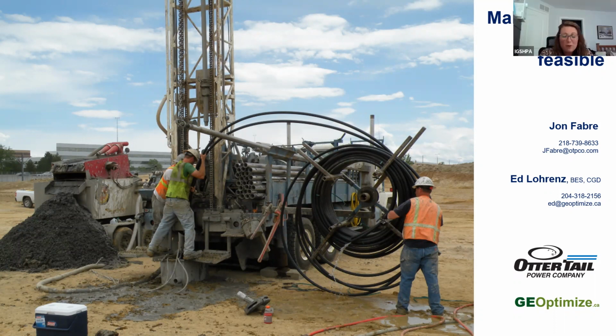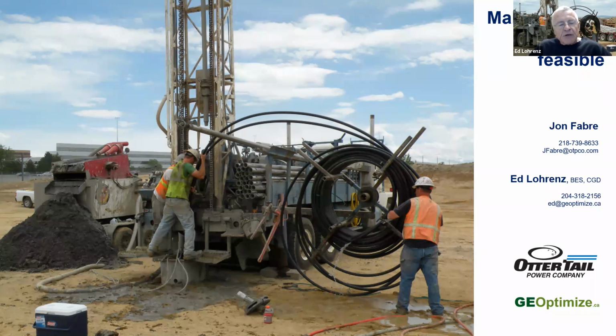Great. So we have one more question. Are bore fields always square or rectangular in shape? And would alternative layouts, such as larger spacing in the center zone or smaller spacing at the perimeters, possibly reduce the size of loop fields? That's a really good question and very appropriate, and it depends to some extent on what the energy balance is. If the energy balance is a fairly even amount of heat you're dumping in and taking out, then a square or close to a square field operates very similarly to a borehole field that might be 2 boreholes wide by 20 boreholes long. If the loads are unbalanced, that's one way you can use to help mitigate that.